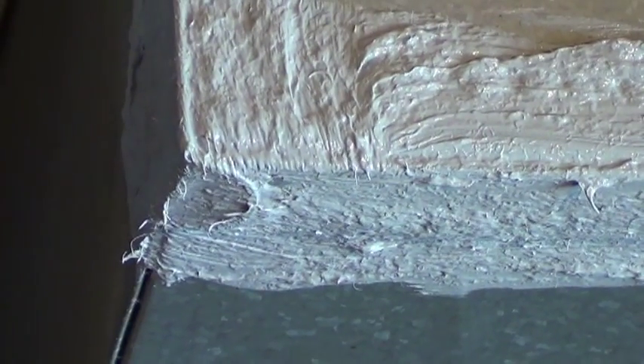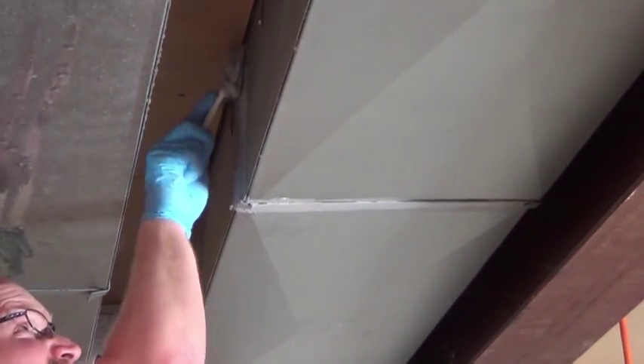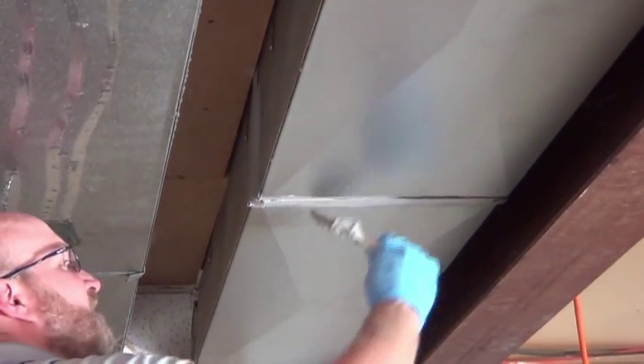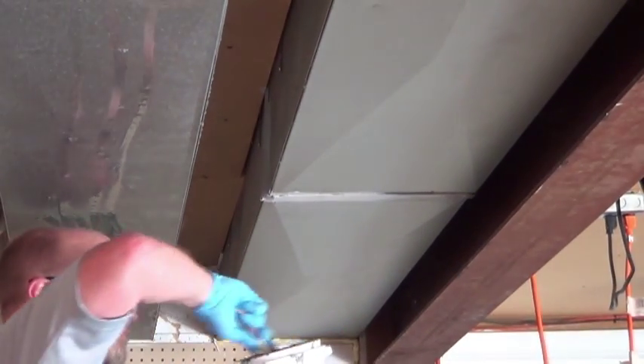Now, ducts in what we call an unconditioned space are the most important to have sealed, because you don't want the air from your house to leak into an attic or a garage or a crawl space. However, any ductwork that you can seal that's got a gap in it should be sealed just for the performance and the efficiency part of it. But again, if it's outside of the conditioned space of the house, the part where you're not heating and cooling, they really have to be sealed and well insulated at the same time.